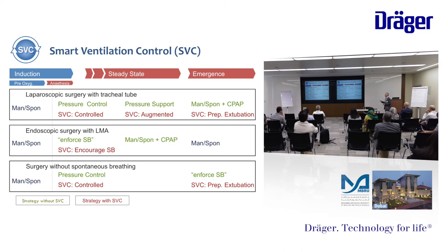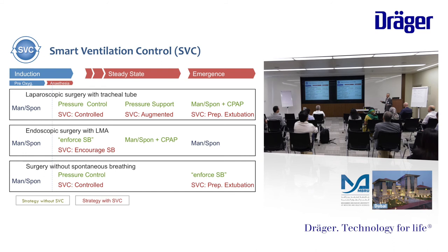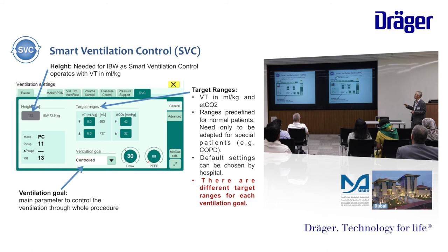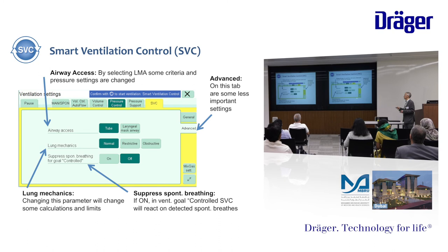And this is what we can do with the smart ventilation control. I just choose smart ventilation control and tell it: my target is controlled ventilation. At the end of surgery, I can tell it: augmented, or prepare for extubation. Here I will choose encourage spontaneous breathing and it will allow the patient to breathe while I assist with pressure support. And here I tell the machine: controlled, then finally prepare for extubation. There are extra settings — the ventilation goal, after entering the patient demographic data, the target range — different target ranges for each ventilation mode as mentioned. These extra settings are not critical at the moment.